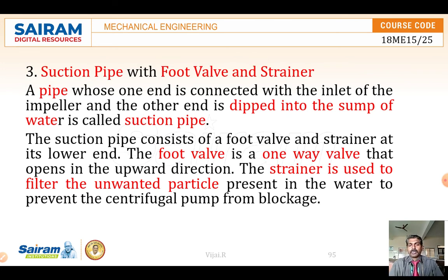So we call it a suction pipe, and when water enters into the suction pipe, the pipe is dipped into a tank full of water. When the electrical motor is switched on, it creates pressure inside and sucks the water. At the bottom, a foot valve and a strainer are required for filtering out other particles. If any particles are there, they will hit the pump when they get into the impeller. So to avoid that, a strainer or filter will be there.